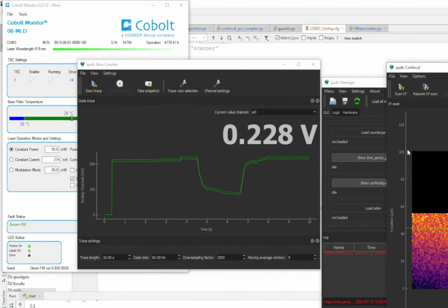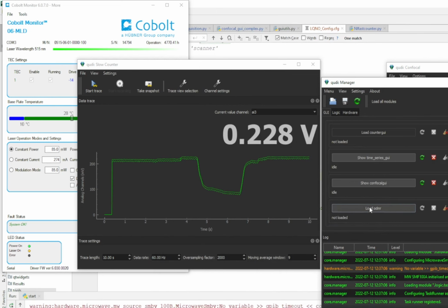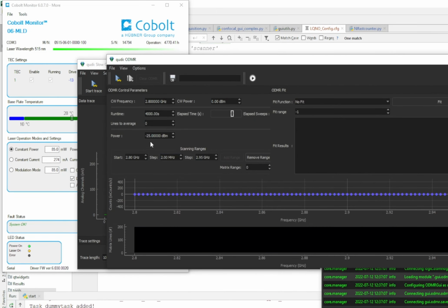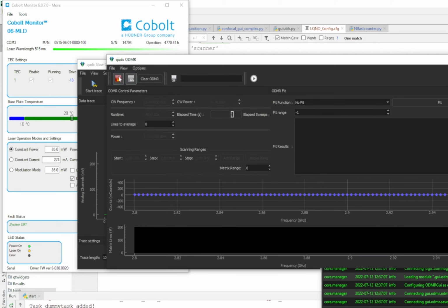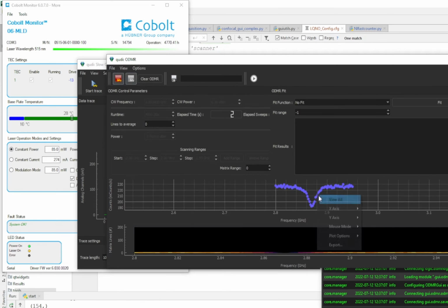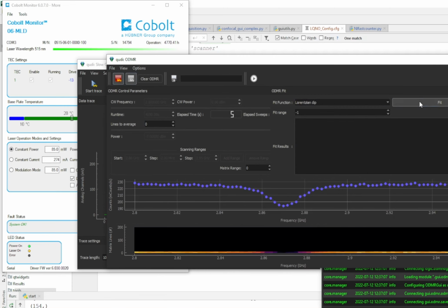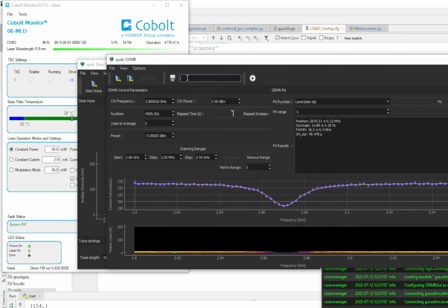And now let's go to the ODMR. In the ODMR, the microwave frequency will be swept. Now let's put, like, -7 dBm for the power of the microwave frequency, and the PL that we showed last is plotted. So you see, at some frequency the PL is reduced, which means that you have this resonance, and we can fit it, and then we can save it.